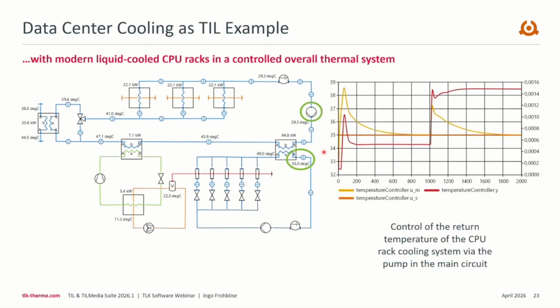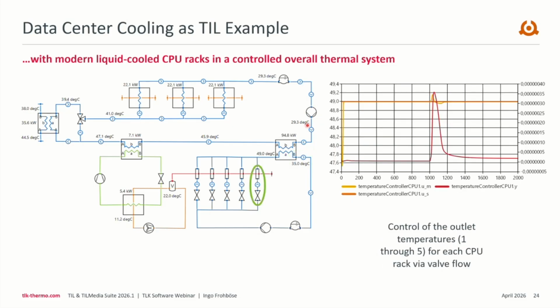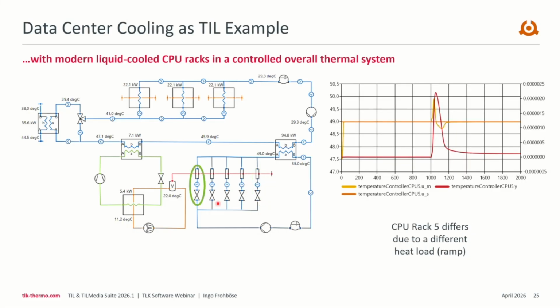We are controlling different things. For example, we can control the return temperature with the pump speed, or the mass flow rate of the pump, and we control each temperature of the CPU racks with the valve opening. In the example, we have a little heat load ramp at the 5th CPU rack to create some dynamics and difference between the five racks.